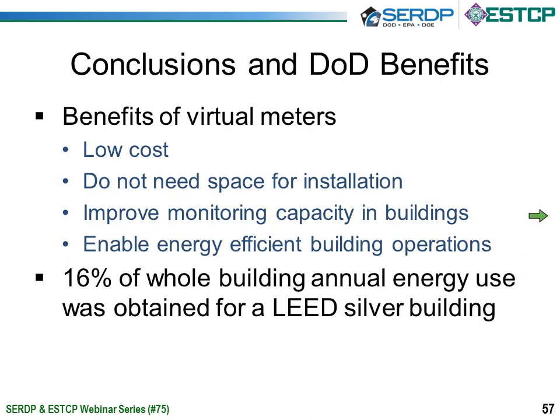So, in conclusion, the benefits of virtual meters, as we've seen a little bit of, are, first of all, low cost. We're using low-cost sensors in place of much more expensive sensors. We don't need the space ordinarily required for the physical sensors to be installed, which is sometimes a problem with HVAC systems. We improved the monitoring capability of the buildings by adding flow rate sensors where we had none before.